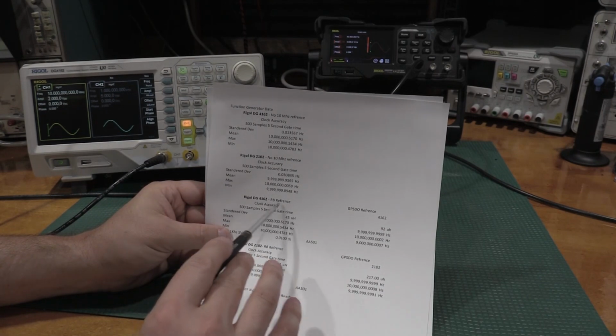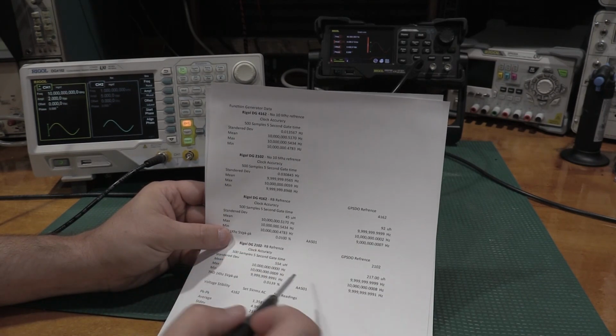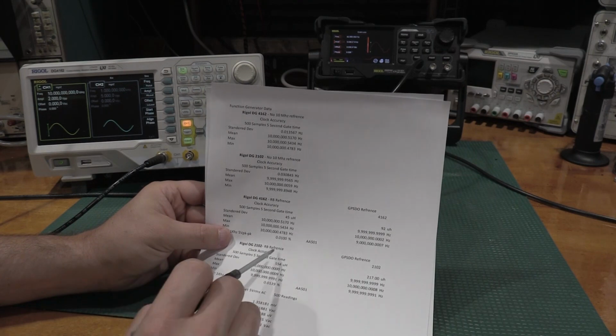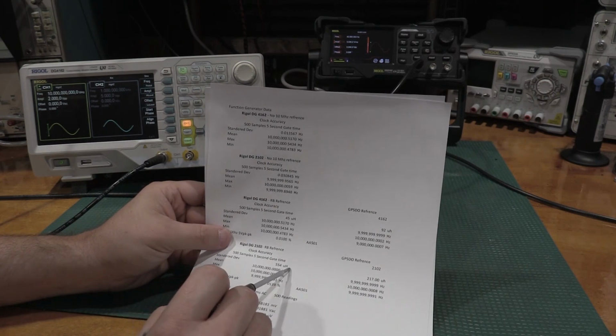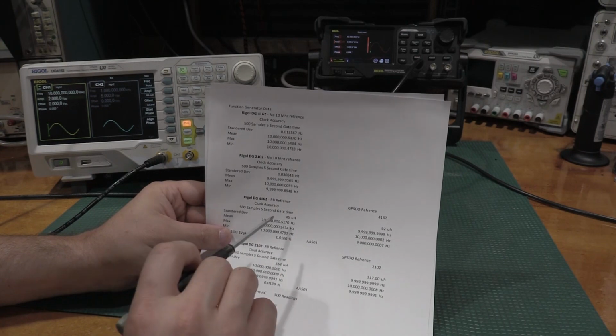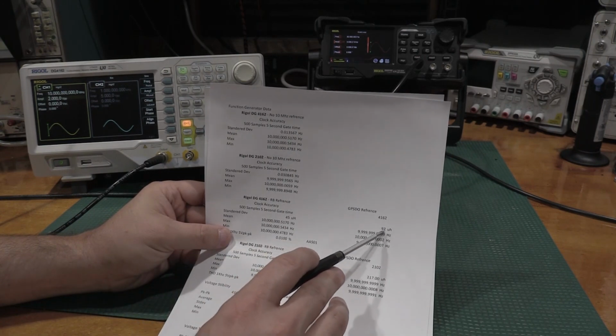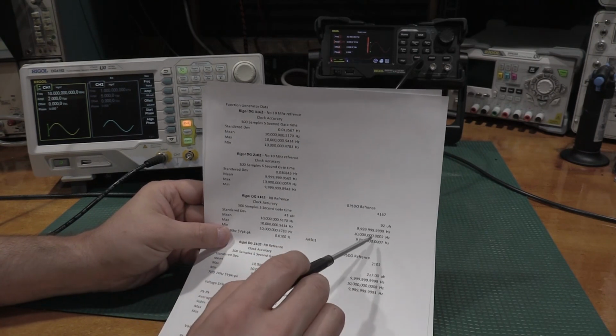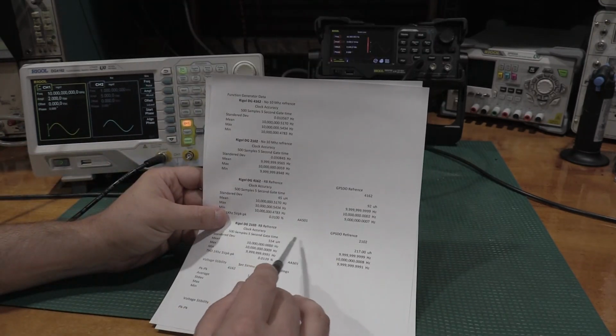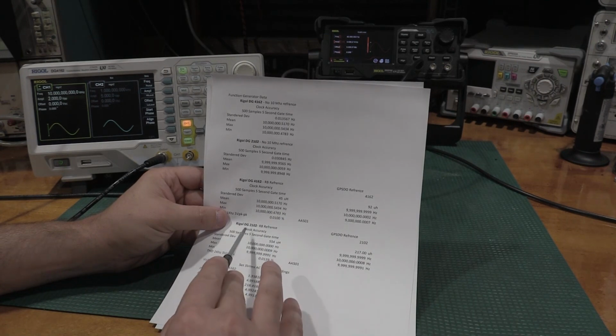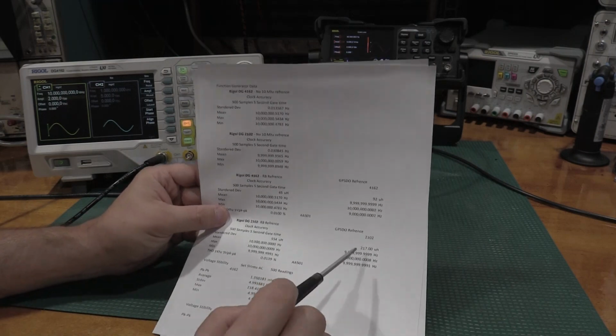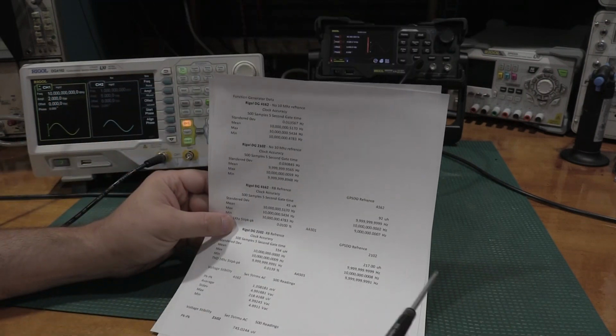And in either case, feeding these a 10 megahertz reference tightened up the clock quite a bit. My standard deviation on the 4162 got down to 45 microhertz. Standard deviation on the 2102 got down to 554 microhertz. Not bad. On the GPSDO, it fuzzed out a little bit on the 4162 at 92 microhertz. And the interesting thing was for the 2102, it actually did better on the GPSDO than it did on the rubidium. So that's an interesting add.